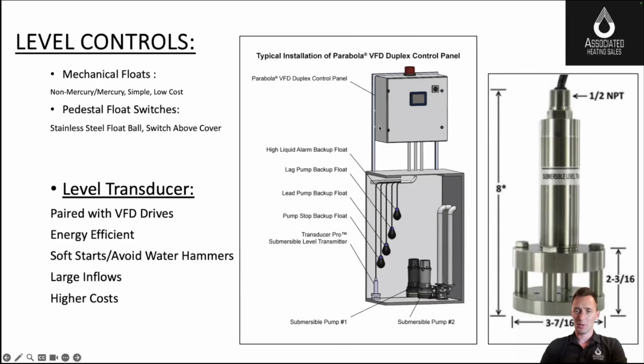The variable frequency drives are typically used in sump or sewage pumps that are high horsepower, so soft starts and soft stops. Say that 10 times. For example, that Coca-Cola job where you had triplex stainless steel pumps. You needed redundancy everywhere because in no way do they need to have their production line go down at all. So level transducer is really nice for that. Soft starts, soft stops, and then redundancy. So this is a nice way to do that. This would be your sort of, you need as much redundancy and reliability as you can get.